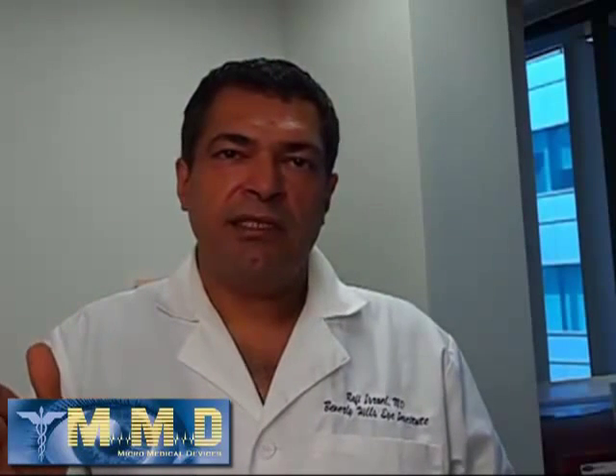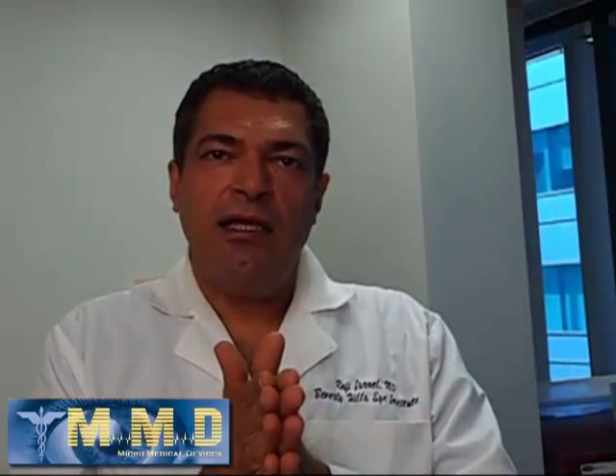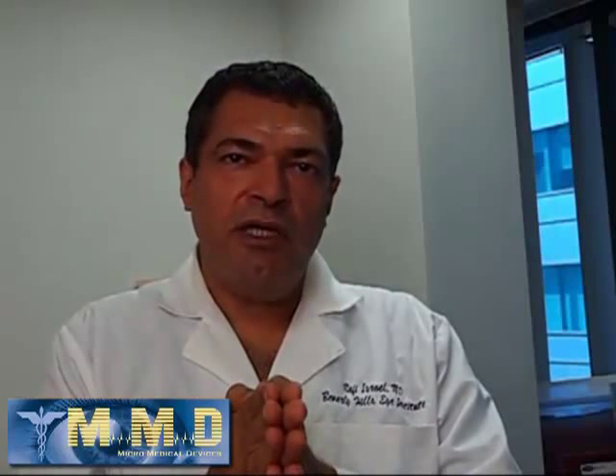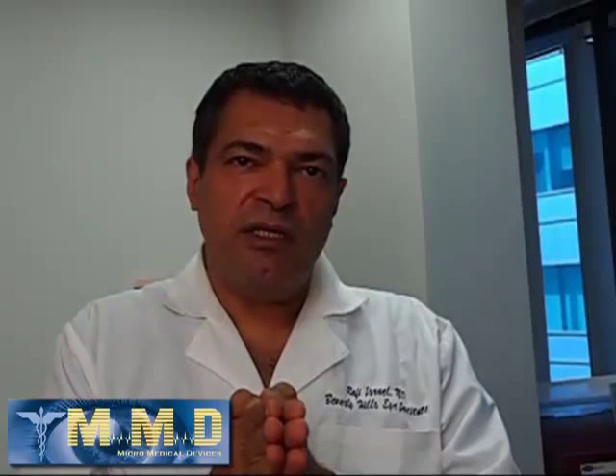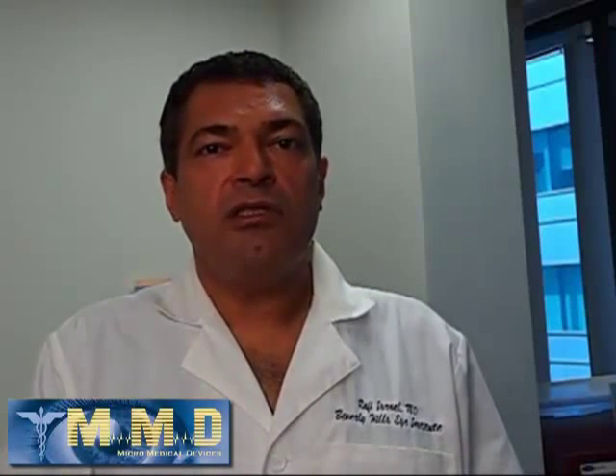You just want the meniscus to touch the cornea, and at that point you want to instruct the patient to look directly at the blinking light and then hold the probe in position until the capture starts. If the capture doesn't start, then the problem could be because of not reaching the thresholds on our echograms, which I will shortly talk about.